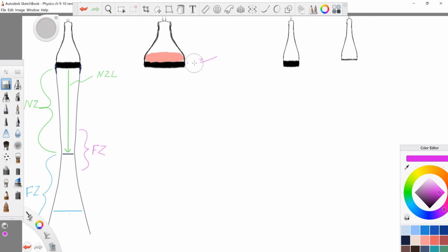But they have a different diameter. The active element is 6 millimeters and 10 millimeters respectively. And the other word for diameter in this case would be aperture. The sound beam of which probe will have a shallower focus? Okay, so we don't really need those numbers, 6 and 10. All it tells us is that one diameter is bigger than the other.